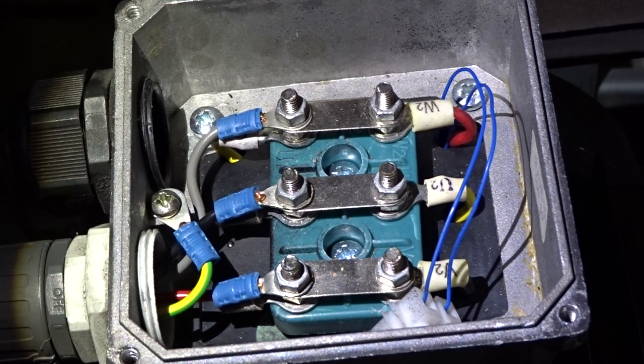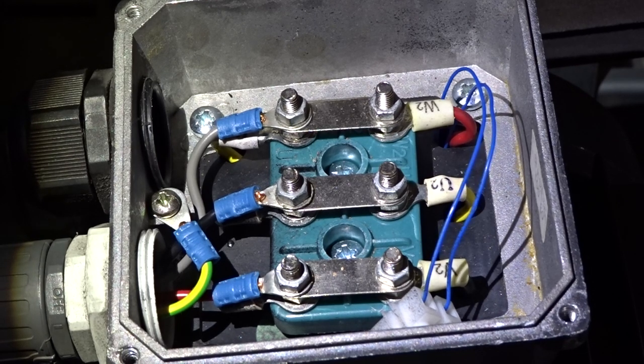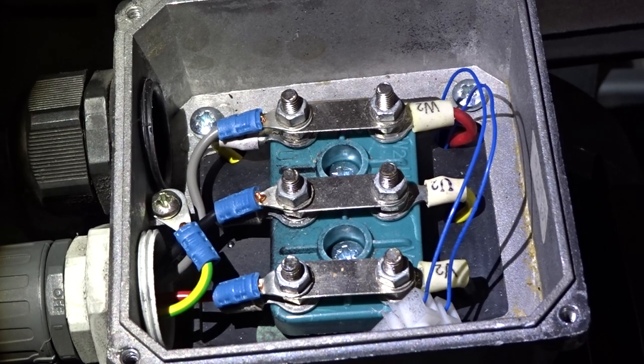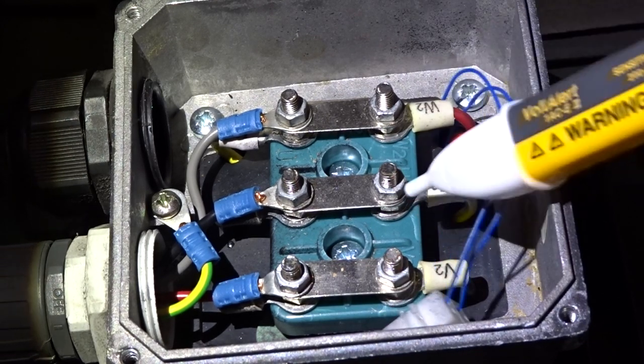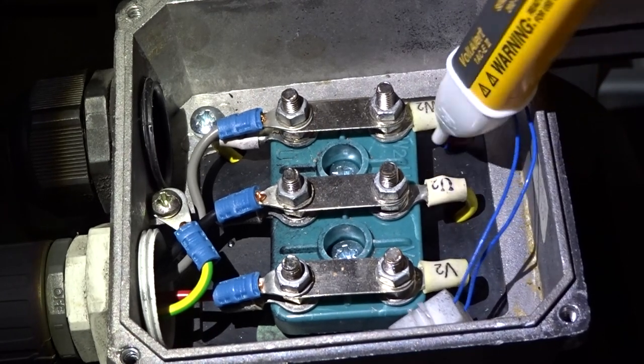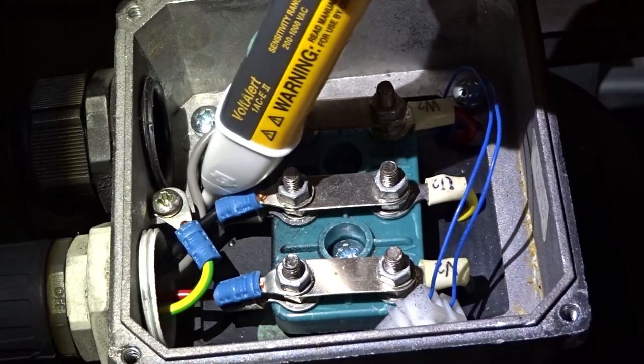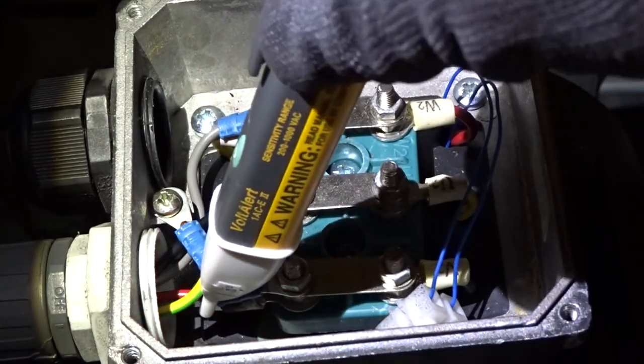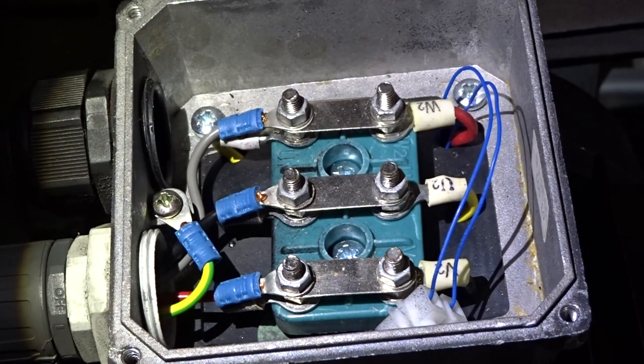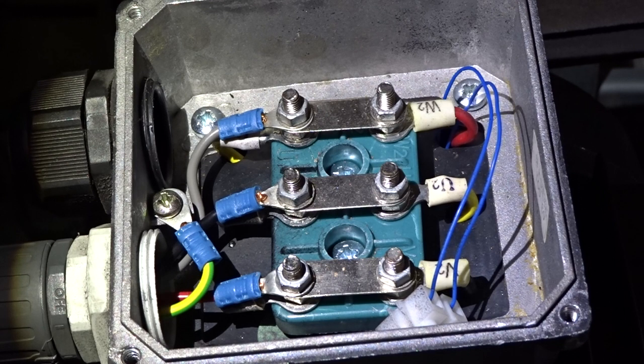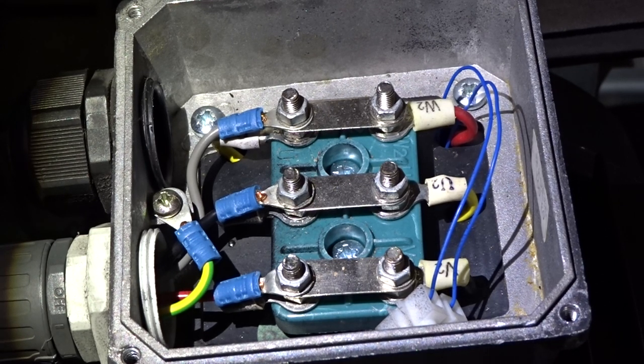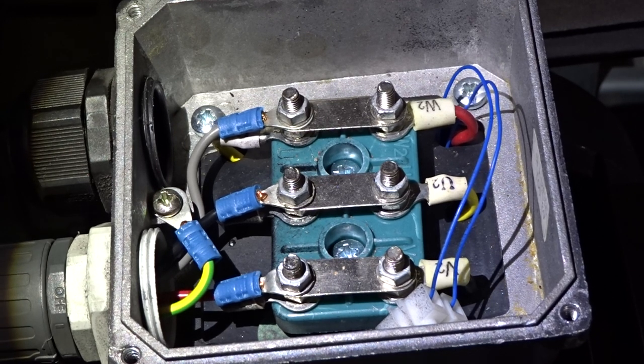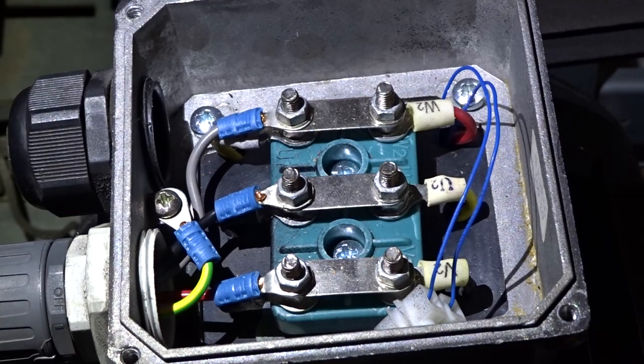So there is no fear of electrocution, but just to be safe you still want to test. Okay, I'm happy there is no power going to this fan. So all I'm going to do now is select the right size tool, check the terminals are tight, and check the wiring for any imperfections.